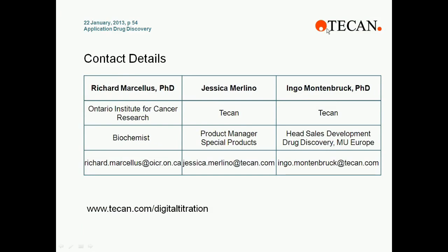There have been a few questions coming in about the slides and their availability afterwards. The presentation slides will be made available after the webinar, and you will be able to download and view the webinar at a later date on demand as well. For those who missed the first half, a question has come in asking how much volume do wells take and how many IC50s can you make from one well? For each dispense head, the user can load up to 10 microliters of compound, and you can dispense that compound into a number of destination plates. At the low end the system can dispense 13 picoliters.